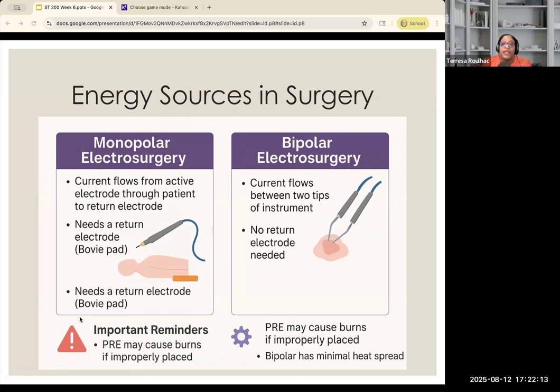Now, we may have one in the room in case we need to switch to monopolar, or if we're doing a case where we're using both bipolar and monopolar, then we're going to automatically put a grounding pad on for safety of the patient. But if the surgeon is using bipolar by itself, there is no need to have that grounding pad or the patient return pad. Again, why? Because the current is only flowing through the tips.